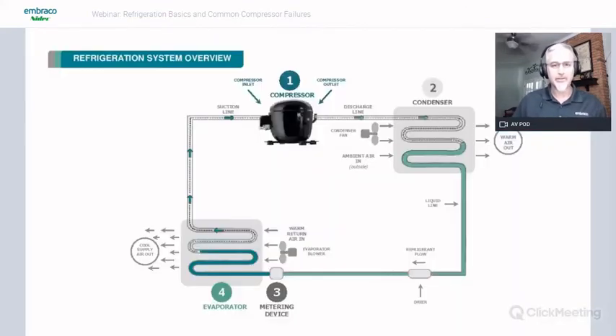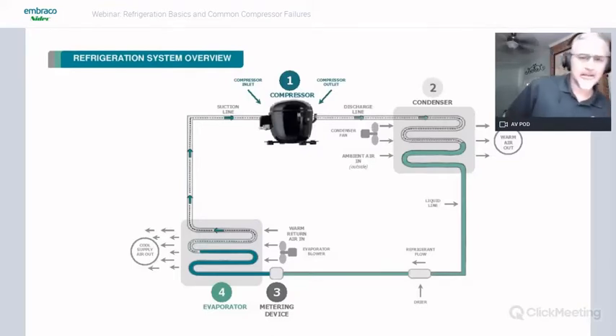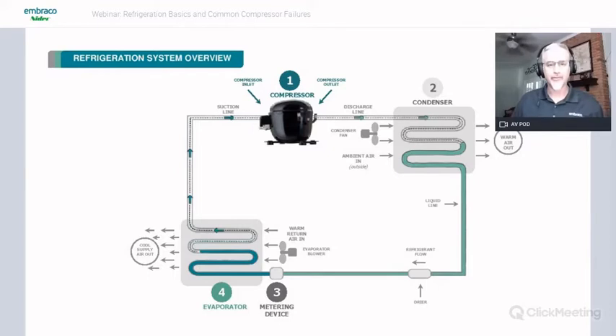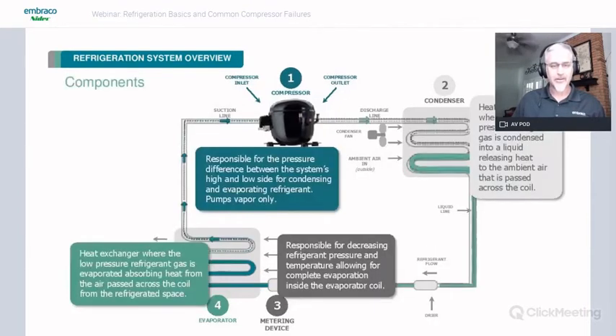And moving on to that refrigeration system overview. This slide shows a basic layout of a very common refrigeration system with the 4 main components that you're going to see in every system. Starting at the compressor, the compressor's main job is to provide the pressure difference between the system's high and low side. And we need that pressure difference for the condensing and evaporating of the refrigerant to do the job of removing heat and delivering it to a place where it's less objectionable.